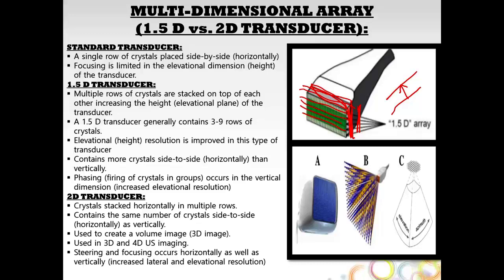And then there's also a 2D transducer. So for this, you have the same number of crystals horizontally as you do vertically. So it's like a square. And what this allows us to do is create a volume in imaging. And so we use these to do 3D and 4D type imaging. And there's going to be steering and focusing not only horizontally, but also vertically. So you're going to get increased lateral resolution and also increased elevational resolution. So there's a lot of advantages to these multidimensional array transducers.